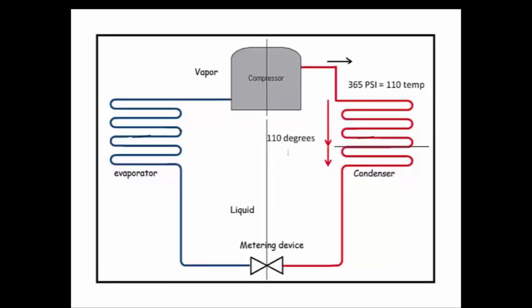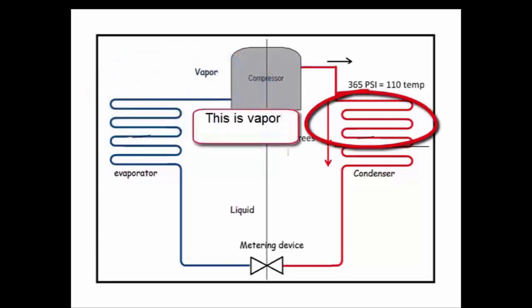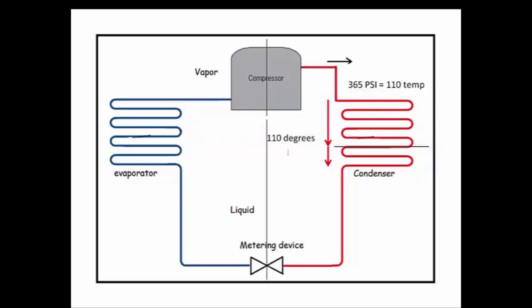So going back to our system here, if things are working perfectly, the temperature of the refrigerant entering the condenser is 110 degrees, which means it's at 365 psi. And as it travels down through the condenser to the black line, it remains 110 degrees. But it's dissipating heat, which is condensing the refrigerant, and it's giving off that heat to the air passing through the condenser.